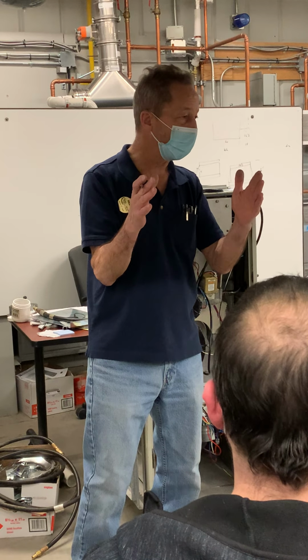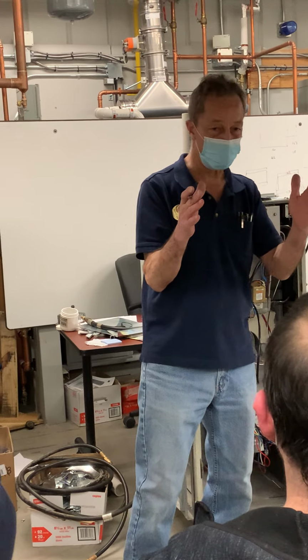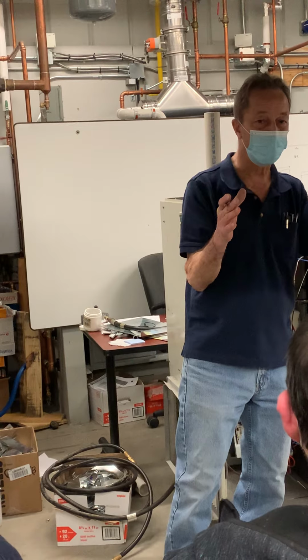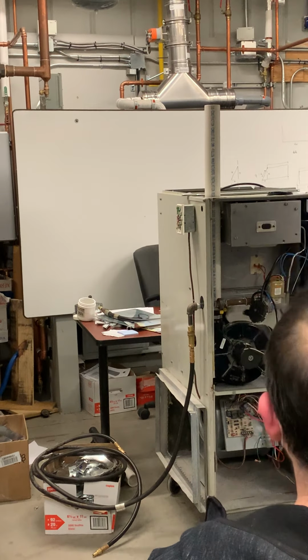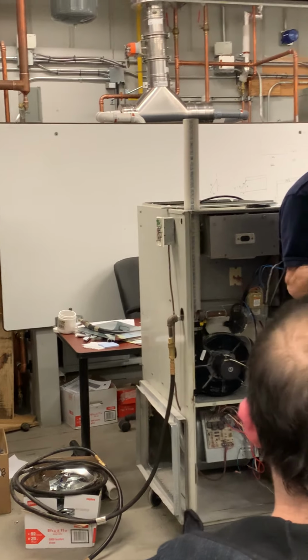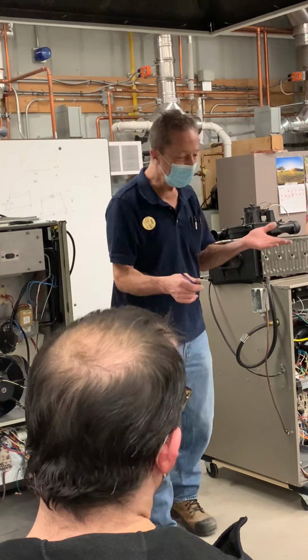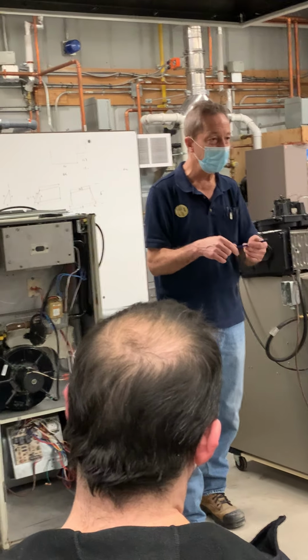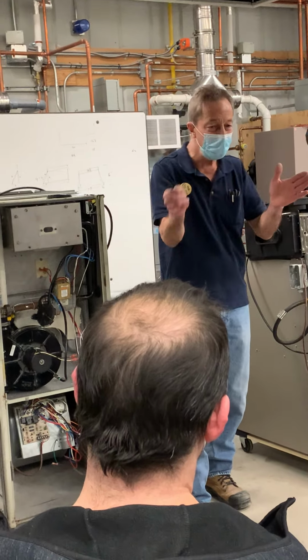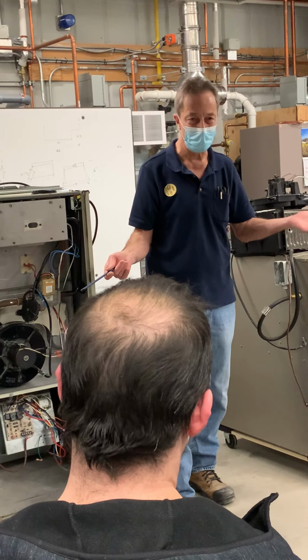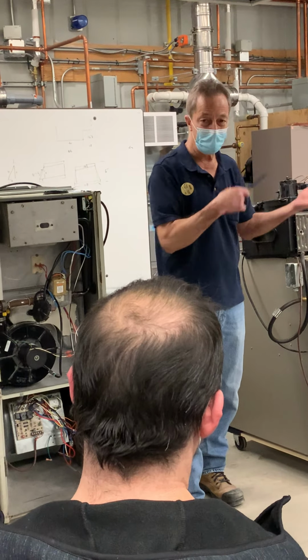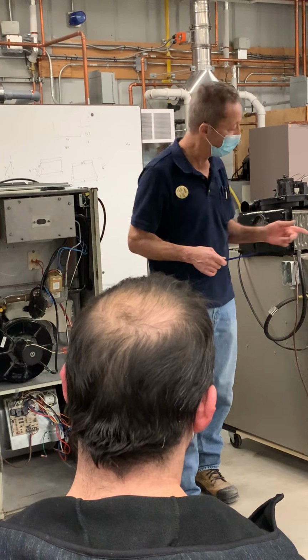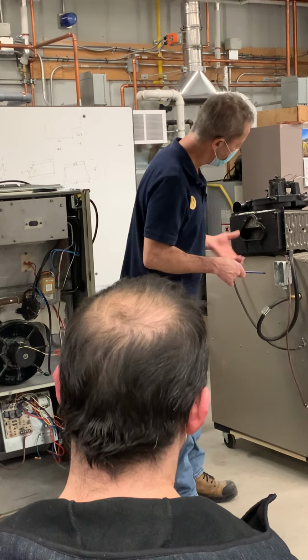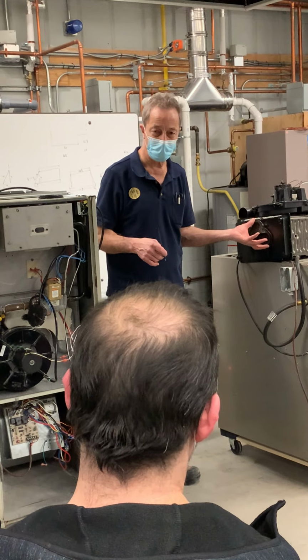You guys, when you're sucking on a straw, are probably doing that, depending on what you're sucking on. If it's one of those McDonald's thick shakes, you're probably sucking a little bit harder. Okay, and that's because on a mid-efficiency appliance or in this hot water tank, the heat exchanger section is wide open. It's really easy to suck the flue gases through. On this one here though, look at it. I got my inducer right here.